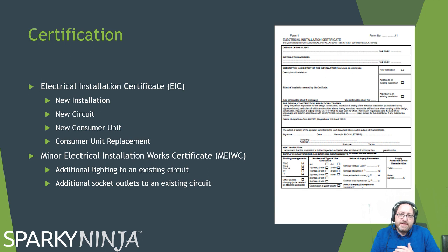With regards to the Electrical Installation Certificate, you've got to know on what occasion that is the needed document. So the Electrical Installation Certificate is needed for any new installation, any newly installed circuits, or if we're going to install a new consumer unit or replace an existing consumer unit. These are the situations where an Electrical Installation Certificate must be done. The other way, the Minor Works, is where we're going to add to existing circuits, lighting or socket outlets, etc. So you must know which certificate for which type of work you will need.